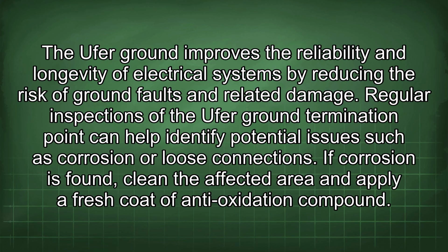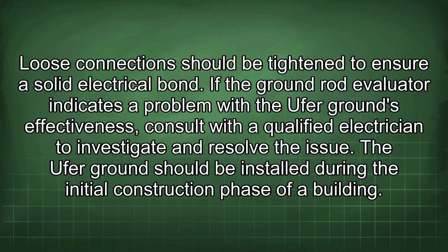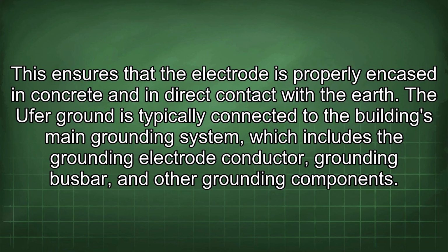Regular inspections of the Ufer ground termination point can help identify potential issues such as corrosion or loose connections. If corrosion is found, clean the affected area and apply a fresh coat of anti-oxidation compound. Loose connections should be tightened to ensure a solid electrical bond. If the ground rod evaluator indicates a problem with the Ufer ground's effectiveness, consult with a qualified electrician to investigate and resolve the issue. The Ufer ground should be installed during the initial construction phase of a building. This ensures that the electrode is properly encased in concrete and in direct contact with the earth.